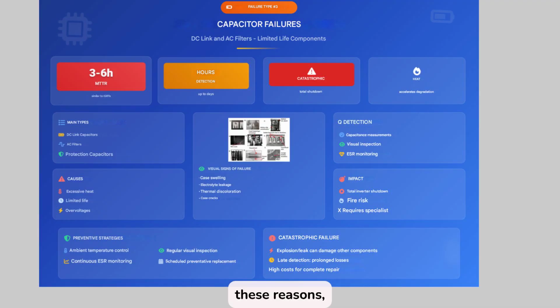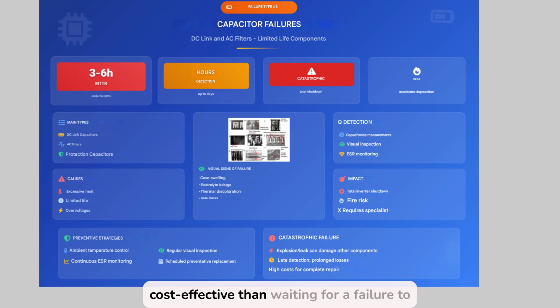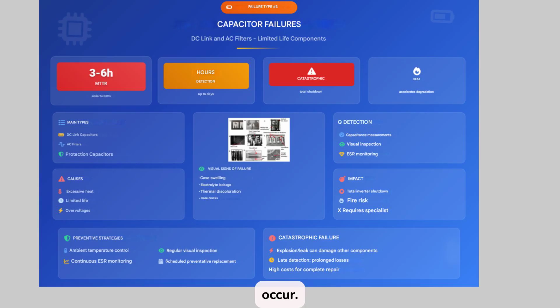For all these reasons, prevention strategies must focus on maintaining a controlled thermal environment, conducting regular visual inspections, and, above all, implementing continuous monitoring of key electrical parameters. Data-driven preventive replacement is much more cost-effective than waiting for a failure to occur. Because, as we often say in the field, capacitors don't give warning. They degrade silently, and by the time they explode, it's already too late.